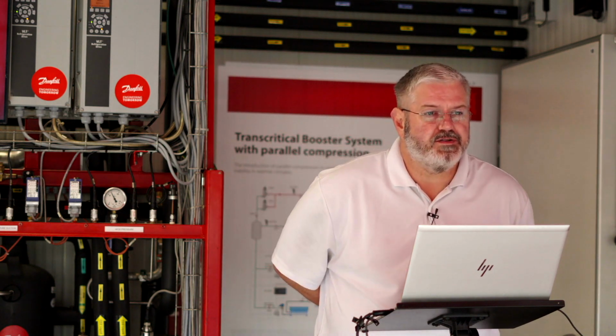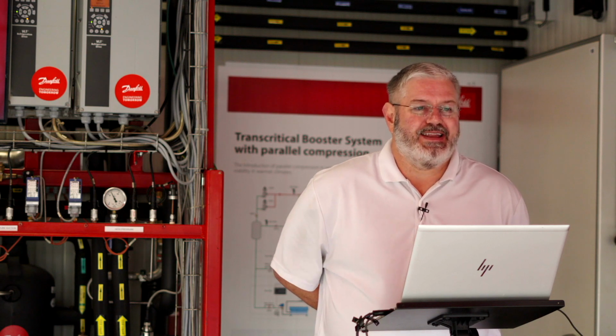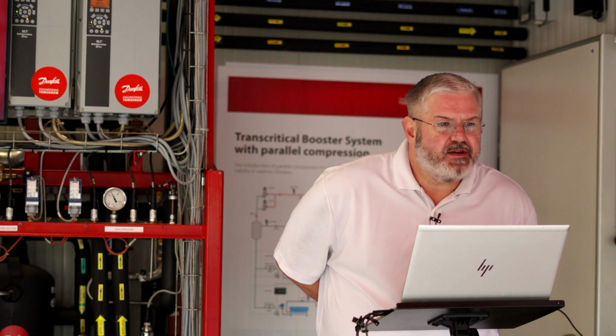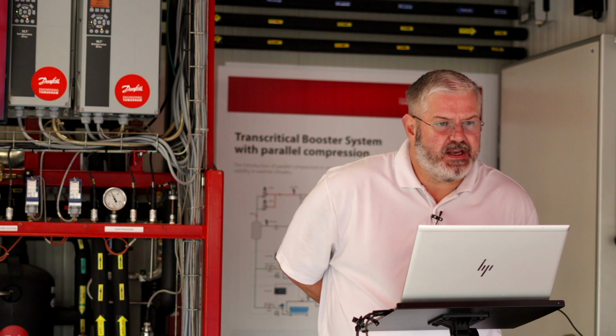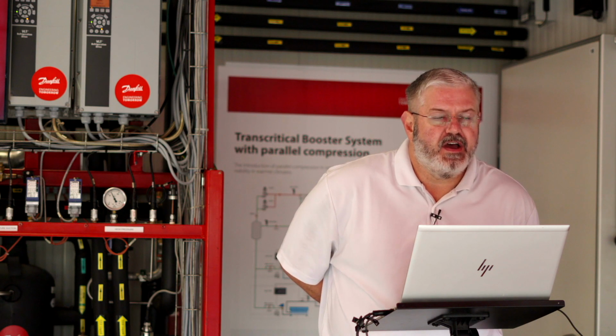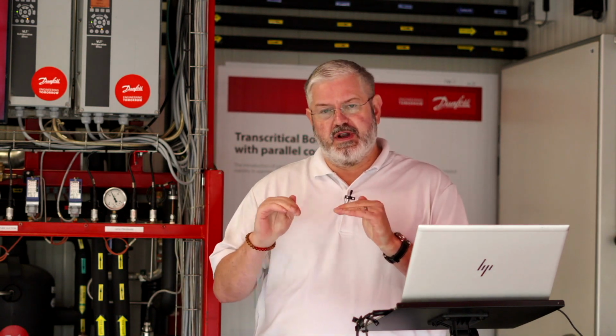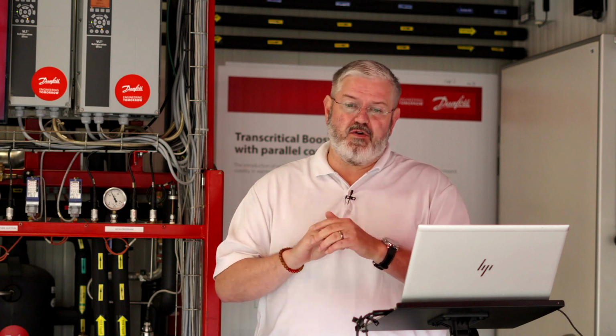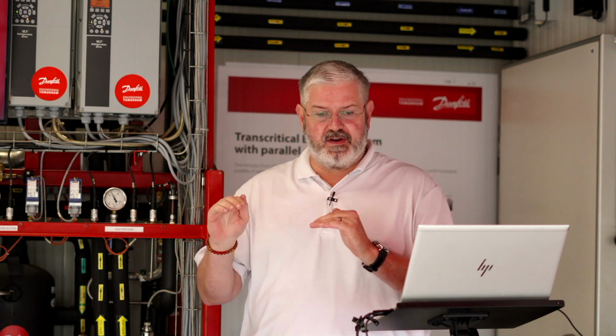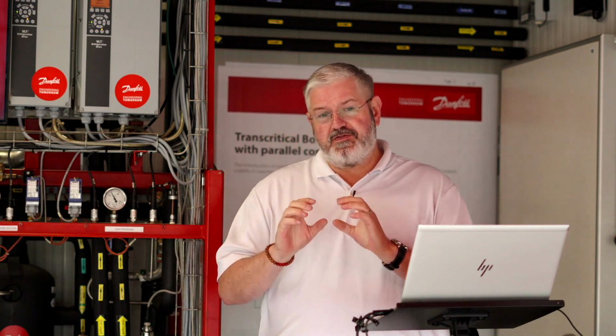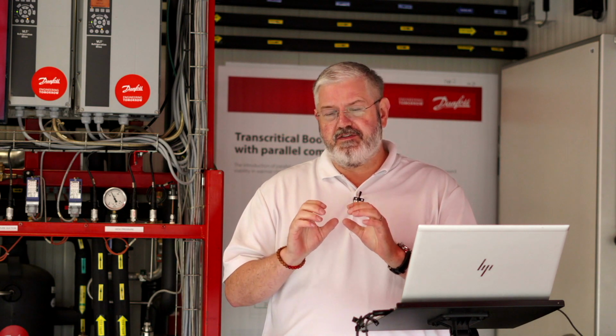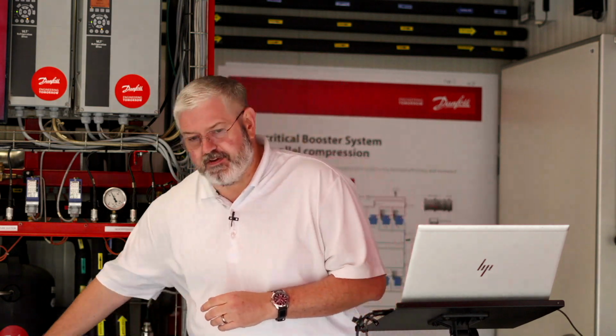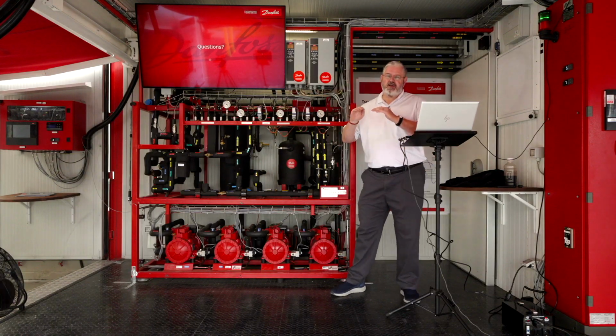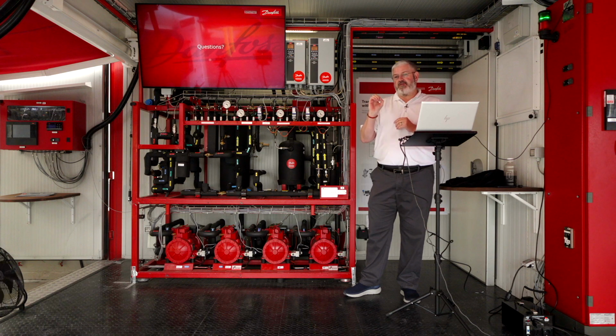Okay, next question is, will low temp compressors always have a lower percent liquid going to the medium? Medium temp has the valve to flash off. Okay, so that's a good question. So the question was, is the medium temp going to get more liquid, or is the low temp going to always get more liquid because the medium temp has to deal with the flash valve? So as far as the liquid feed going to the cases and the actual expansion valves, that's coming off the bottom. That's coming off of our flash tank, where our liquid's above the bottom sight glass. So we've got a solid liquid feed going to the store for both medium temp and low temp.